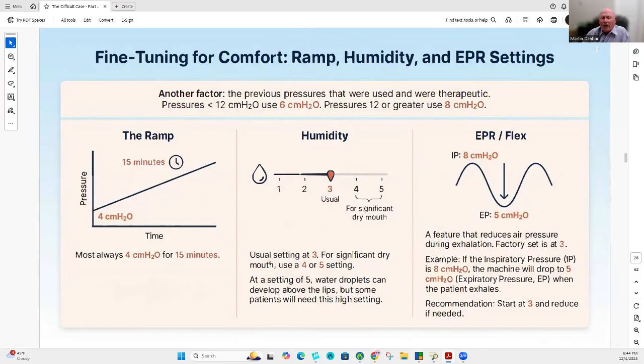Humidity, I have found that normally 3 is accepted. All CPAPs have a water tank, and you want to set the water at a level so that the humidity goes through the hose and moistens the inside of the mouth and nasal passages, etc. I personally have mine on 5. Actually, sometimes on patients, when it's at 5, they'll get water drops on their mustache or on their face. But here again, I normally start people at 3. I don't go 3 to 5 immediately unless they're really dry. You want to do it slowly.